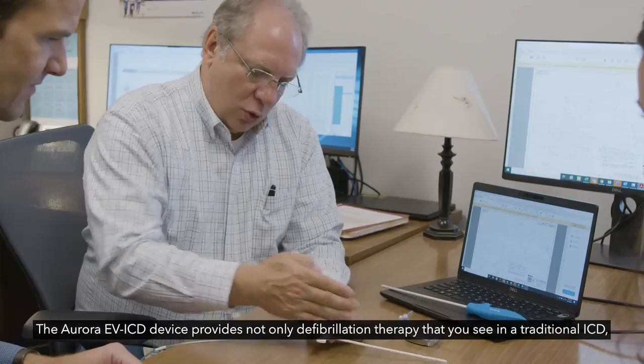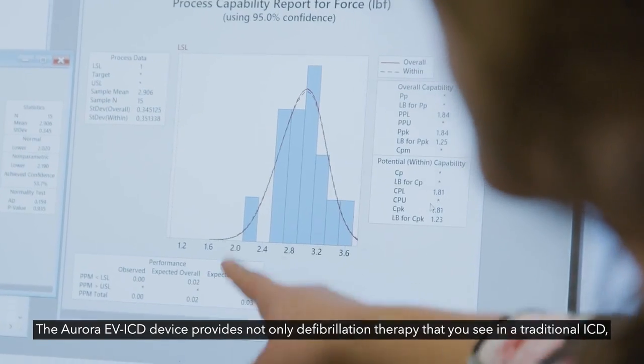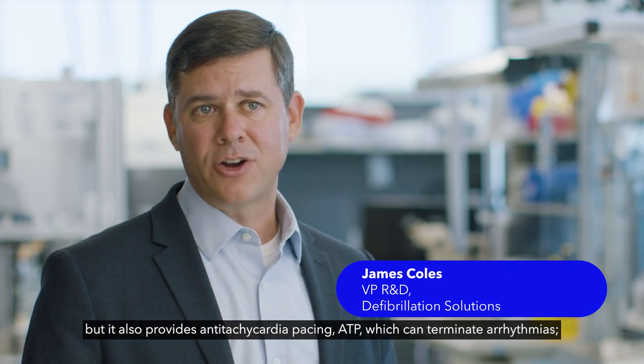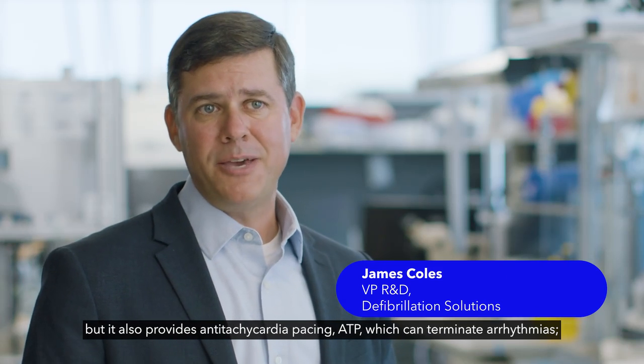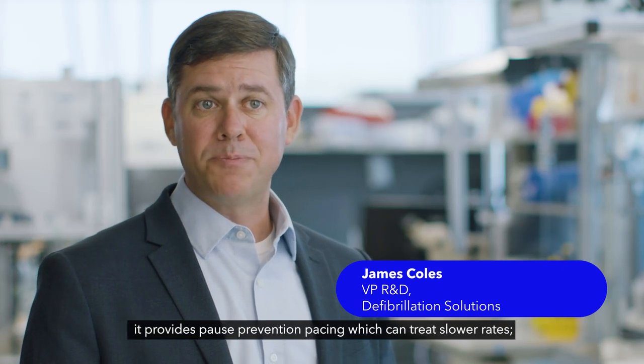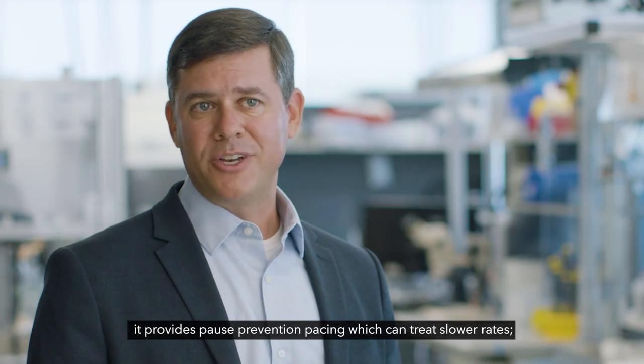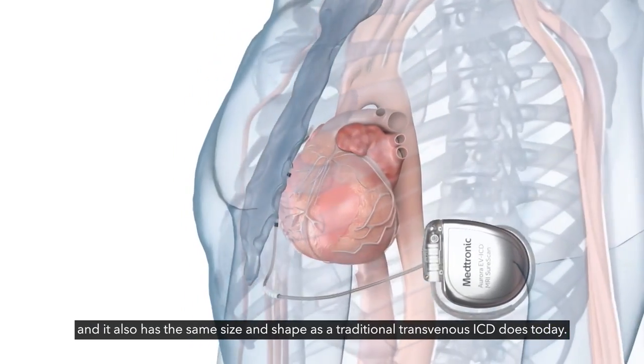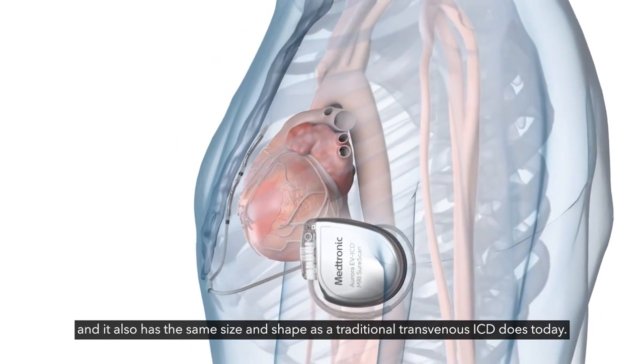The Aurora EV-ICD device provides not only defibrillation therapy that you see in a traditional ICD, but it also provides anti-tachycardia pacing — ATP — which can terminate arrhythmias. It provides pause prevention pacing, which can treat slower rates. And it also has the same size and shape as a traditional transvenous ICD does today.